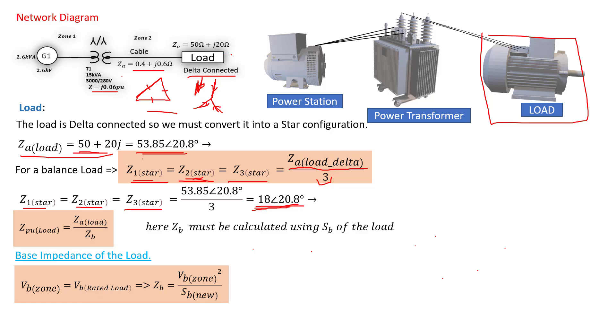V_B zone must equal the V_B rated of the load. Imagine a motor rated for 230V AC — the transformer must supply exactly 230V, no more, otherwise the motor windings will overheat. So V_B zone must be what's rated for that load. Because the rated value isn't given here, we calculate V_B zone using the formulas from tutorial one. If you haven't watched tutorial one yet, please click the link on your screen to catch up. Replacing all the values, we get V_B zone equal to 242.67V.